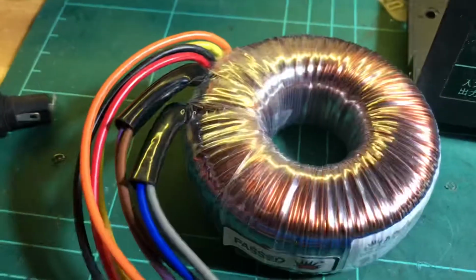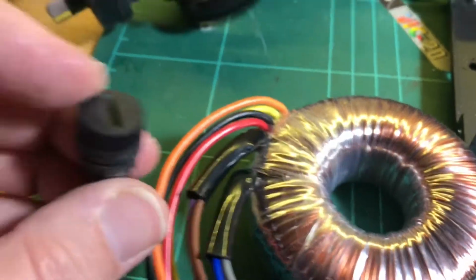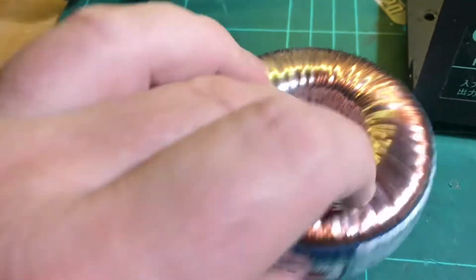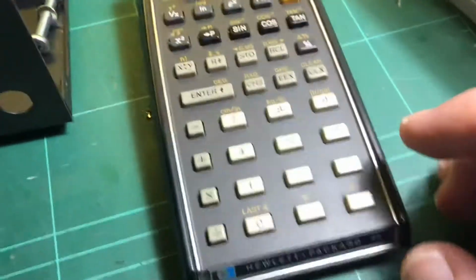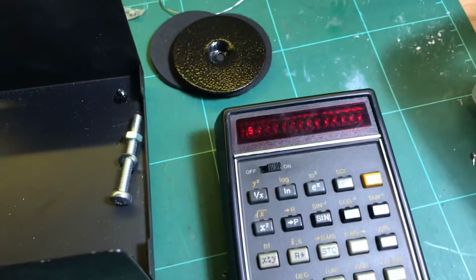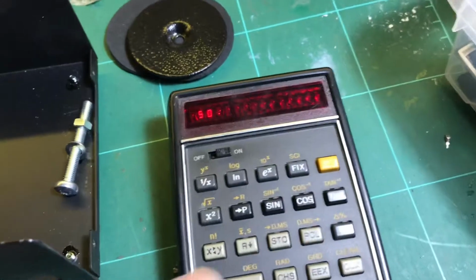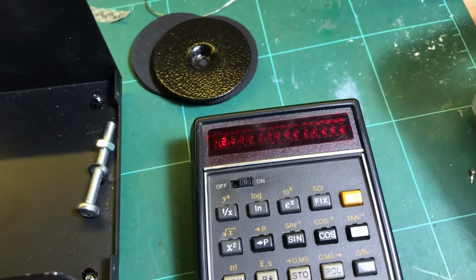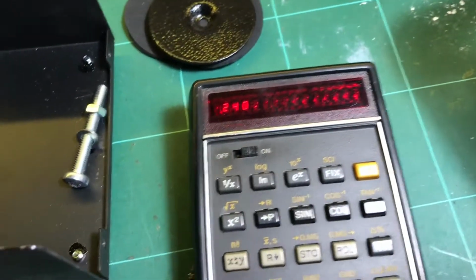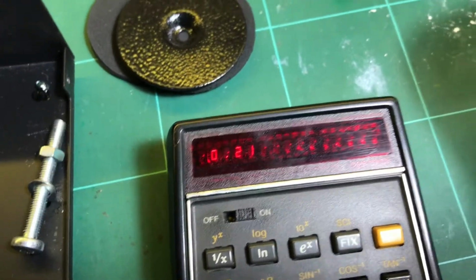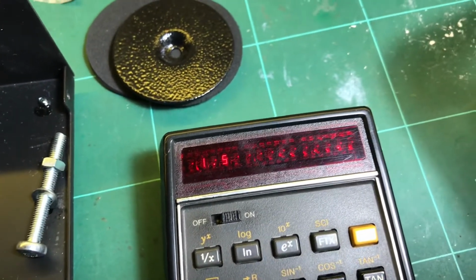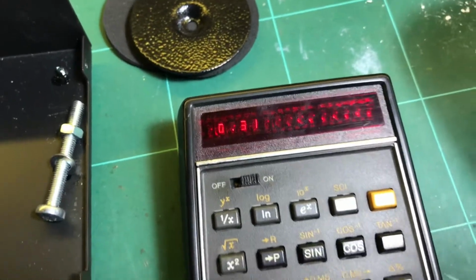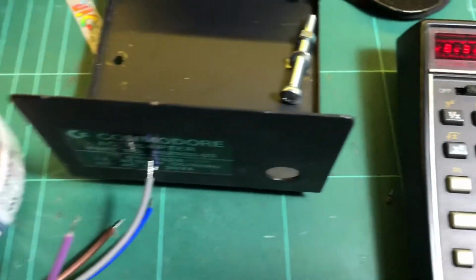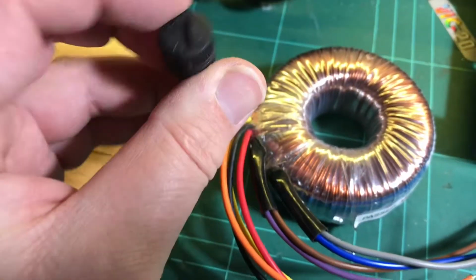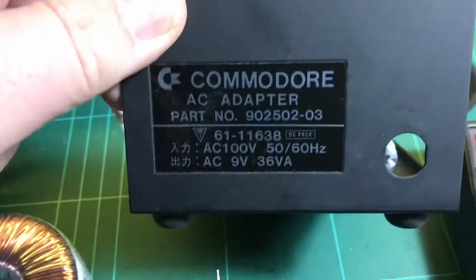The first thing it said was, reading up on it, there can be a large inrush current or something. So for the fuse, it reckons it's 50 volt amps divided by 240, isn't it, divided by 0.21 amps, and then 150%, so 0.31. So I have a 0.315 slow blow fuse.